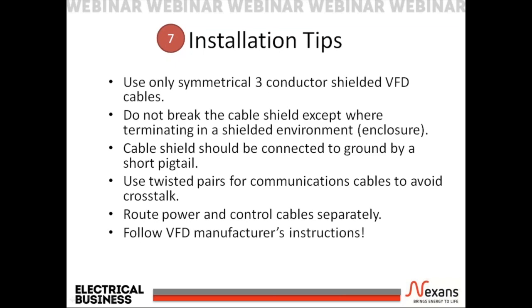Route power and control cables separately. Many of the VFD manufacturers have minimum acceptable distance suggestions between cables. See their product literature. Follow the VFD manufacturer's instructions. These are critical to a successful, trouble-free installation. They are the experts when it comes to drives.